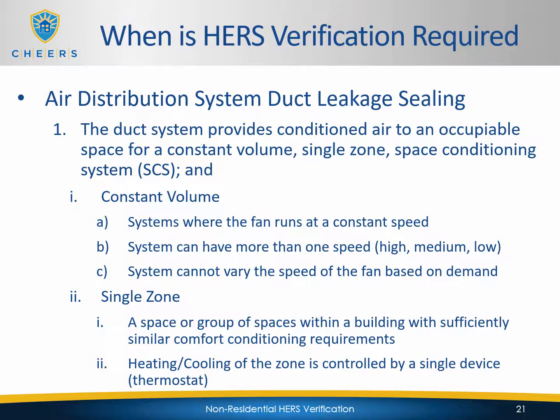So it's the same thing in a non-residential building, more where you have a warehouse space connected to office space. If you have a single system that is serving those two zones that are somewhat different, then that would not be a single zone. So we're looking at just the office space or just the warehouse space. Those would be single zones.